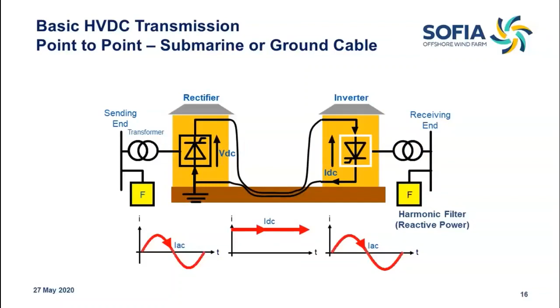On the question of why choose DC: at the time the decision was made, this graph shows the trade-off between distance and cost. For an AC system, the orange line, you have a basic cost for the offshore and onshore substations, plus a cable cost that increases almost linearly with length. For DC, you have a much higher cost for the converter stations because they're bigger—the offshore converter station for Sofia is well over 10,000 tonnes—but a more modest cost per metre for the cables. So there is a break-even point, which for submarine cables is somewhere in the region of 50 to 80 kilometres.